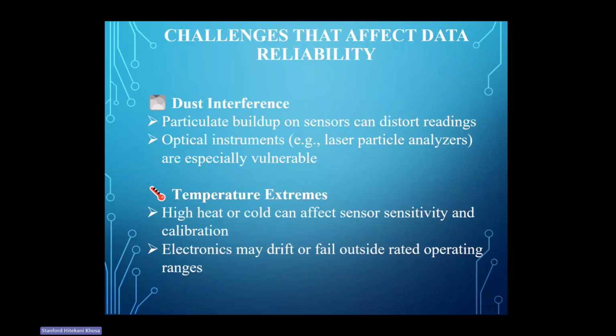This is why some instruments recommend a seasonal calibration, to ensure that what we have on our calibration file caters for the difference in temperature, because temperature does have an impact on what we measure. And with that said, this is the reason why calibrations are needed.